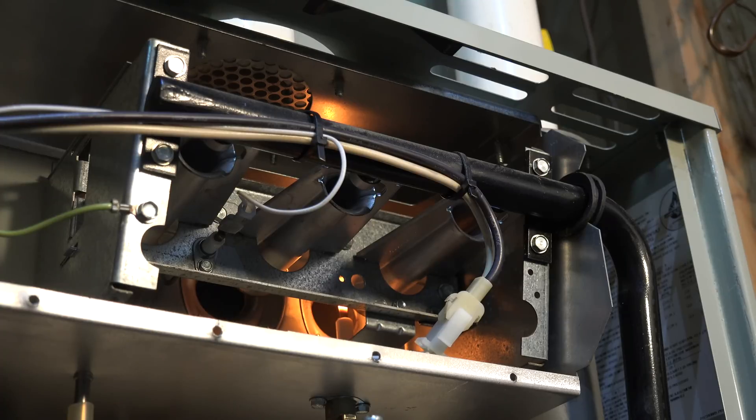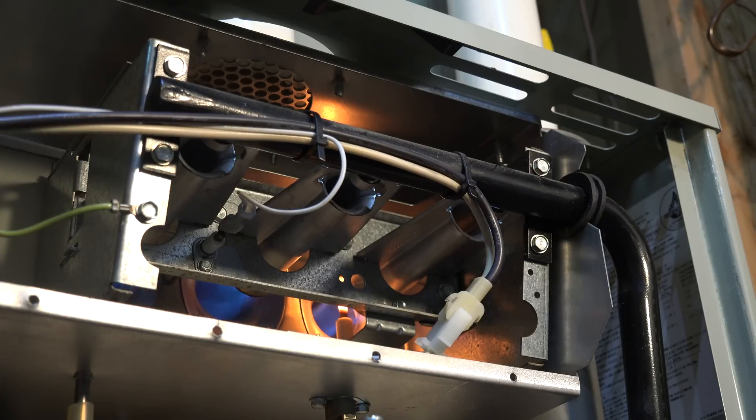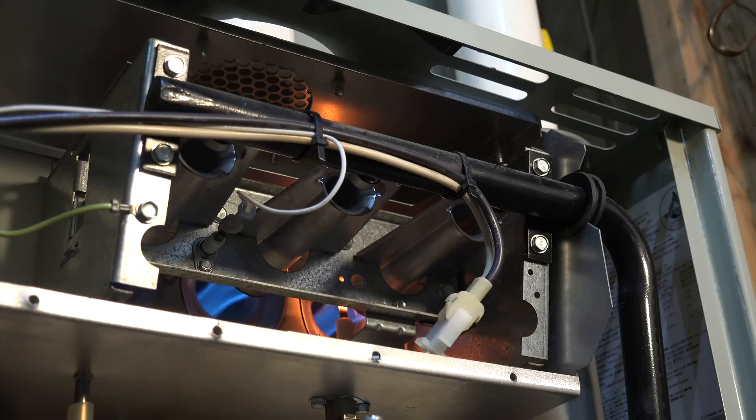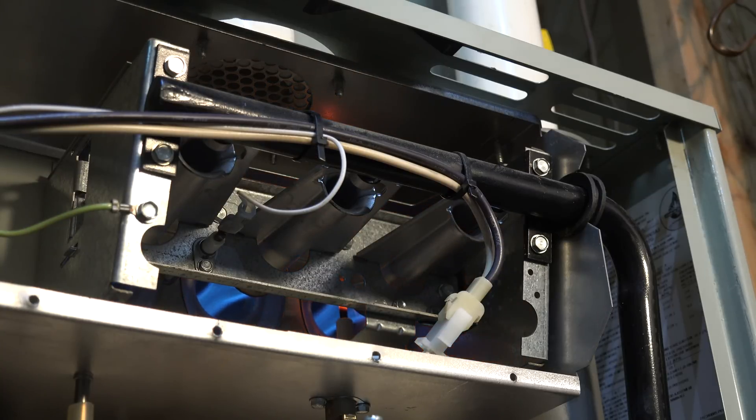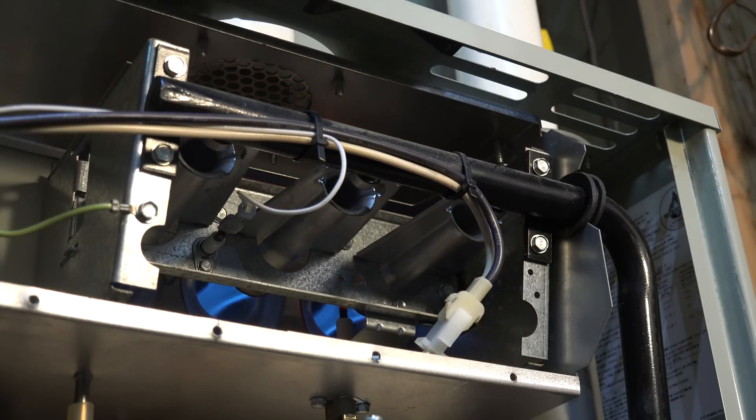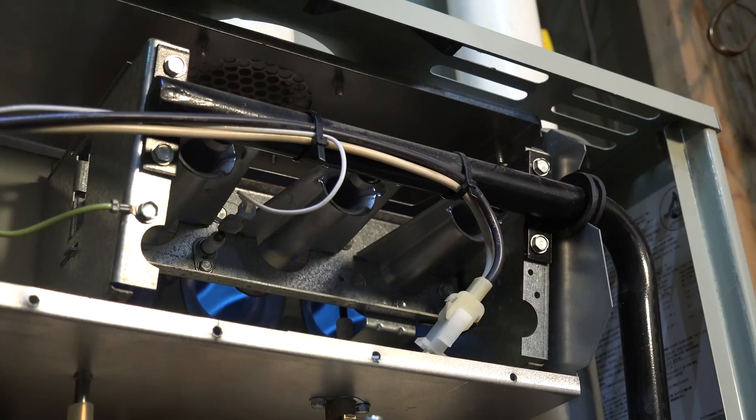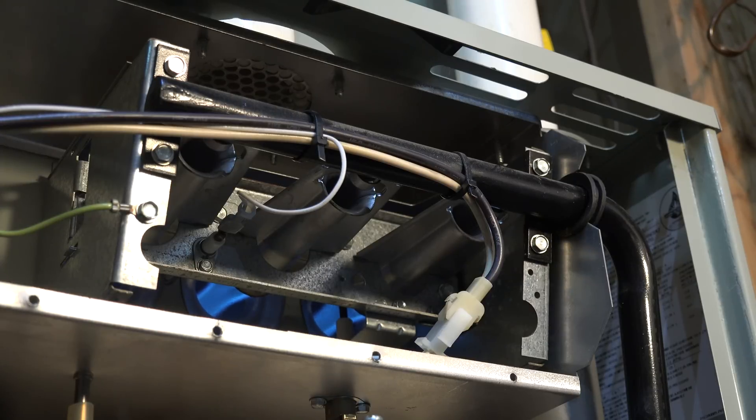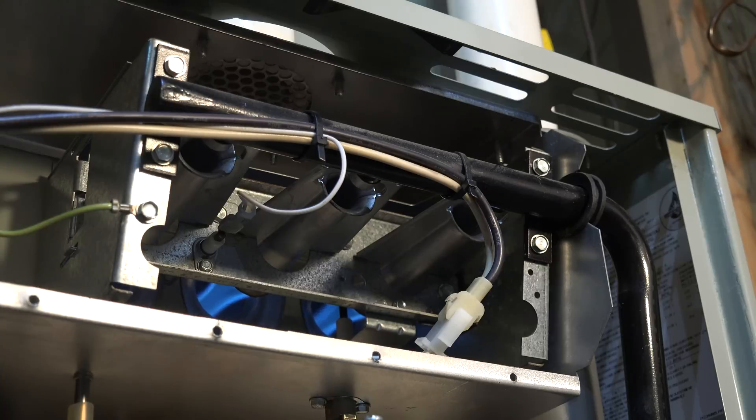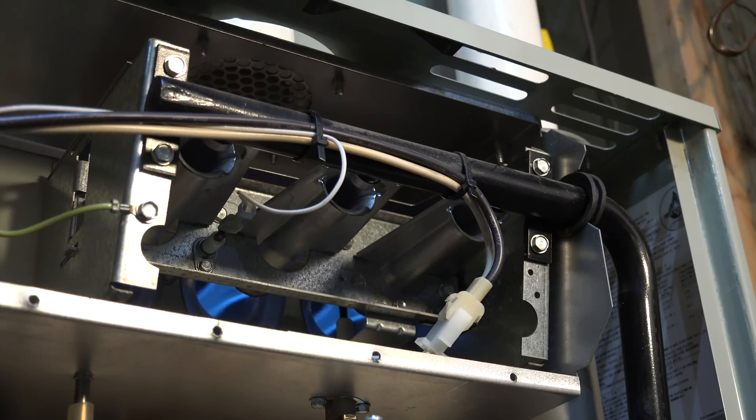Okay, you can see it's on. The burner is lit and they're staying lit. So look at it close. I can't really get close enough with this camera, but look close at it. Be sure the heating is even throughout the hot surface igniter. And of course, the flame has stayed on.